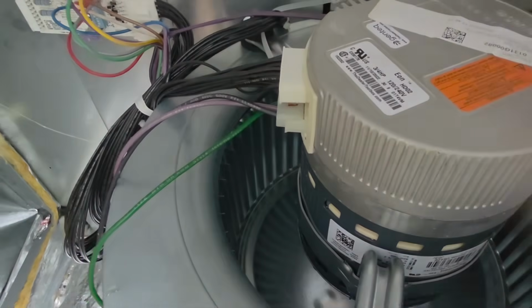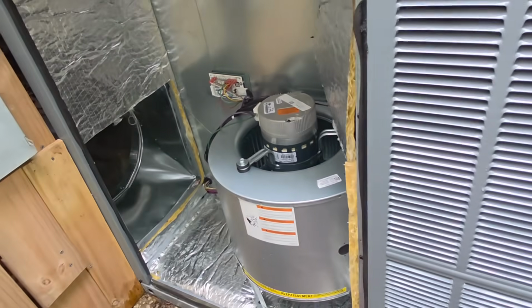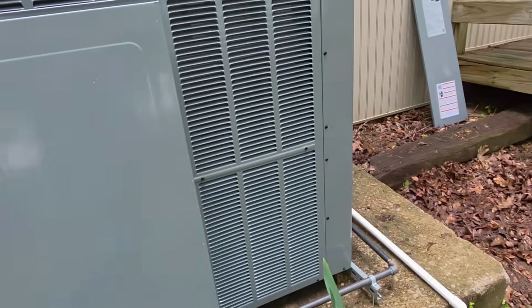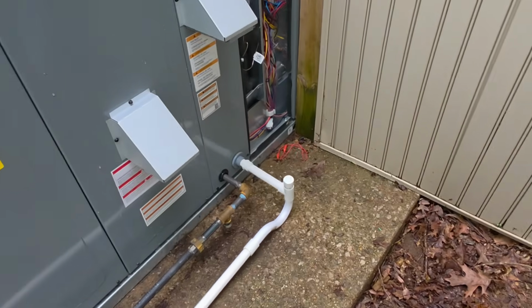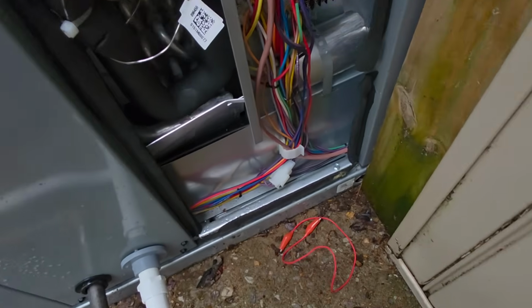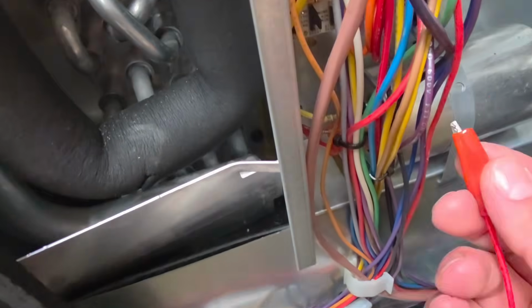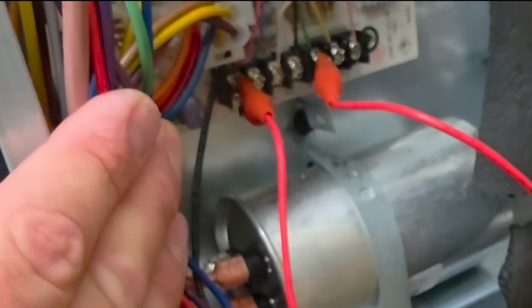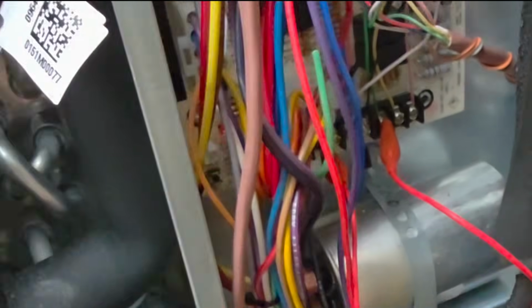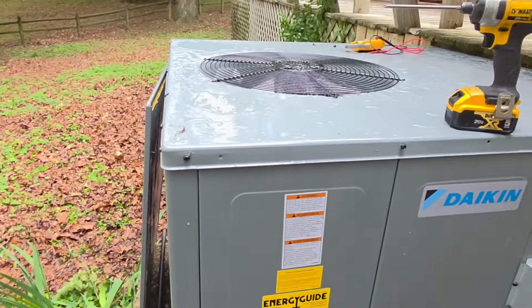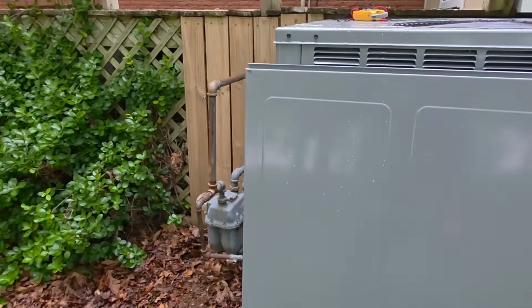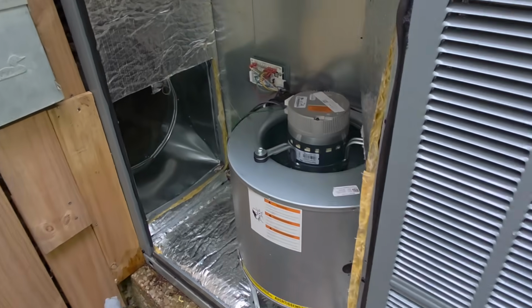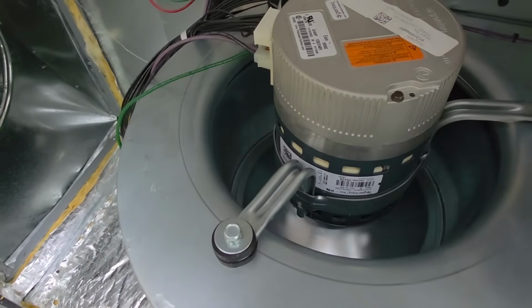Put everything back together. Blower does not have a call. Now let's go to the thermostat wires and let's use our alligator clip. We went from R to G. So we gave that blower a call and it should come on. It should start running. There it is.